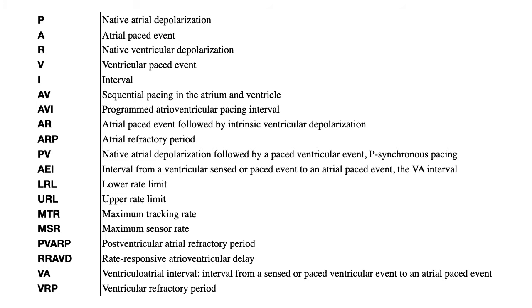The AR stands for the atrial paced event followed by the intrinsic ventricular event. The ARP is the atrial refractory period. The PV is the native atrial depolarization followed by a paced ventricular event, which is called P synchronous pacing. The atrial escape interval, or the ventricular atrial interval, is the interval from the ventricular sensed or paced event to an atrial paced event. Lower rate limit, upper rate limit, maximum tracking rate, maximum sensor rate, post-ventricular atrial refractory period or the PVARP, rate responsive AV delay, and the VRP is the ventricular refractory period.